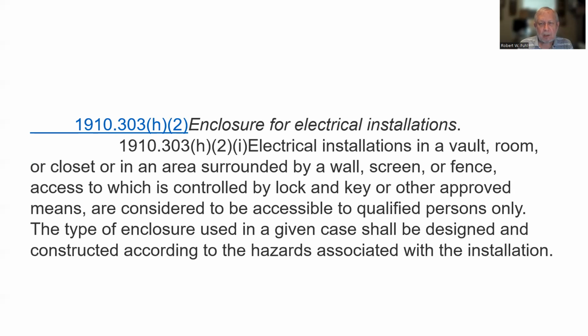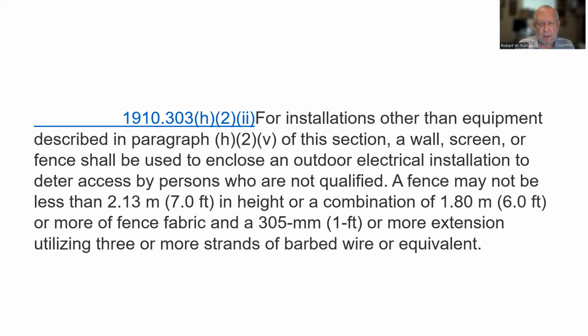Enclosure for electrical installations. Electrical installations in a vault, room, or closet, or in an area surrounded by a wall, screen, or fence, access to which is controlled by lock and key or other approved means, are considered to be accessible to qualified persons only. The type of enclosure used in a given case shall be designed and constructed according to the hazards associated with the installation. For installations other than equipment described in paragraph H2V of this section, a wall, screen, or fence shall be used to enclose an outdoor electrical installation to deter access by persons who are not qualified.